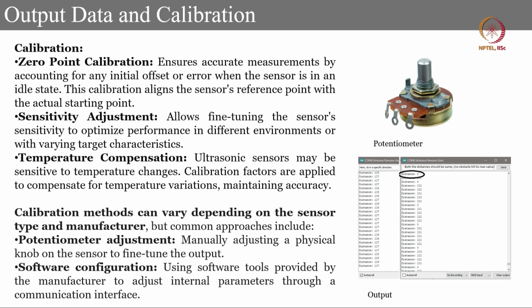So, the calibration can be zero-point calibration, which is to ensure accurate measurement by accounting for initial offset or errors. Sensitivity adjustment allows fine tuning of the sensor in different environmental conditions. Temperature compensation: an ultrasonic sensor may be sensitive to temperature, and calibration factors are applied to compensate for temperature variations and to maintain the accuracy. The calibration methods can vary depending on sensor type and manufacturer.